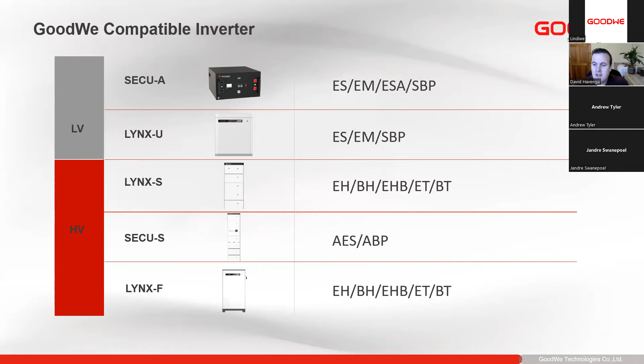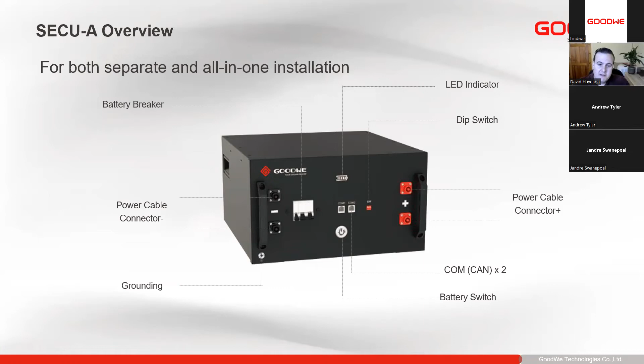The SECU-As are the batteries which are designed to go in our all-in-one, our ESA, but they can also be used separately. As you'll see, the device has a battery breaker, the LED indicator for the SoC, as well as error codes and things like that. We have the negative power cables, the positive power cables, and we have our comms. So the comms, one is to the inverter and the other one is to the next battery. There's also a grounding point here, and then the on button.